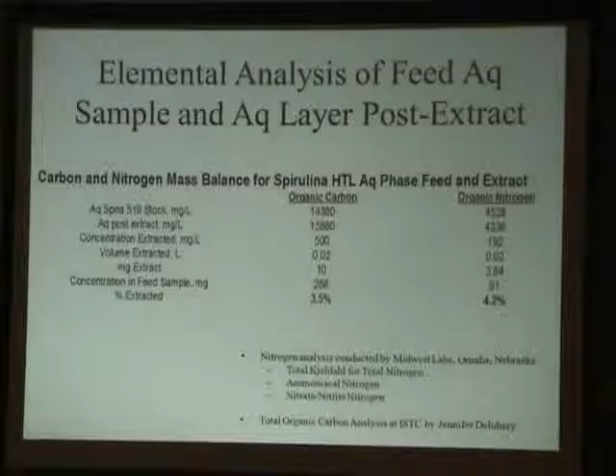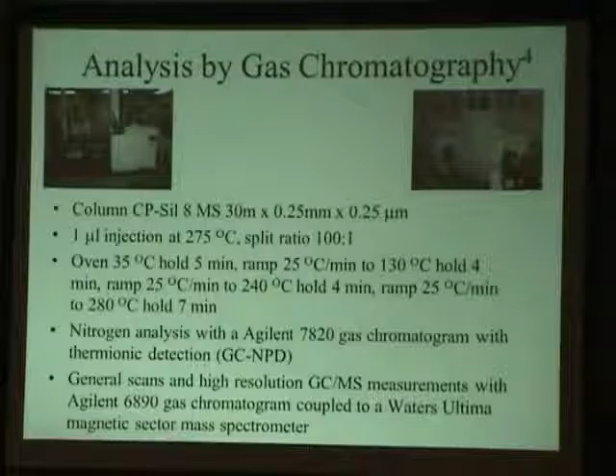So then, also I followed their gas chromatograph parameters from that paper. This is my operating parameters, the column, my oven ramp. We ran it on two different instruments. We ran it first on a nitrogen phosphorus detector, a thermionic detector. It's specific to nitrogen and phosphorus. And then also we ran it on our high-resolution magnetic sector GCMS. That's this beast right here.